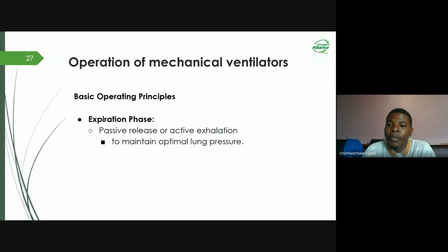After the inspiratory phase, the ventilator transitions into the expiratory phase. The inspiratory valve closes and the expiratory valve opens. During expiration, the patient passively exhales, and the ventilator allows the air to flow out of the lungs. The expiratory valve controls the release of gas, which maintains a positive pressure in the airways to support lung function. Another thing I want to mention is that the rate of expiration is also an important parameter, and it is influenced by factors such as the resistance of the patient's airways and also the compliance of the lung tissue, which is of course directly proportional to the elasticity of the lung.